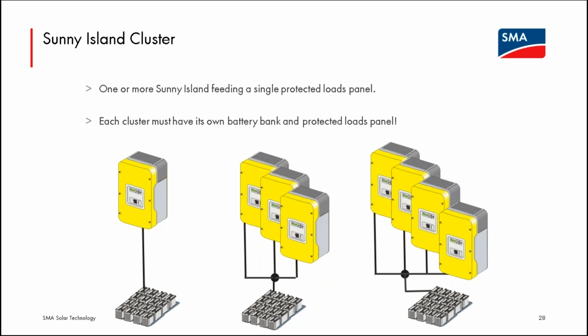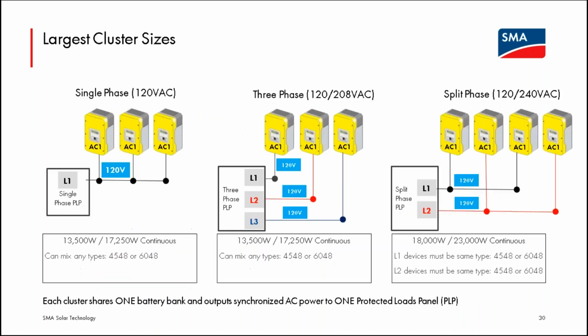When you program these devices, one device is labeled as the master, programmed as the master. All of the Sunny Islands have that functionality, but setting the others as slaves means they will take cues from the master, and the AC waveform outputs of multiple Sunny Islands will be synchronized so that all of the AC power of multiple units can be driven to one loads panel, and a split phase or three-phase grid can be easily created. An important thing to remember is each cluster of Sunny Islands must wire to one and only one battery bank. Again, the slaves all just listen to the master.